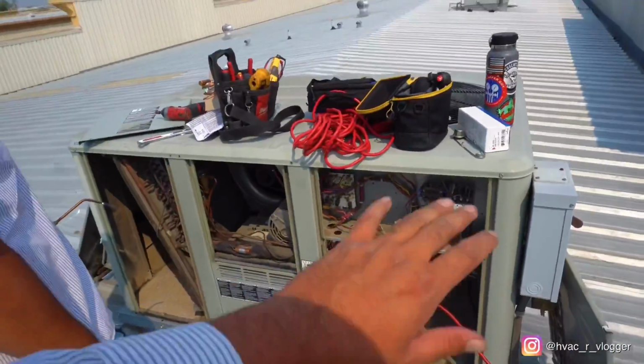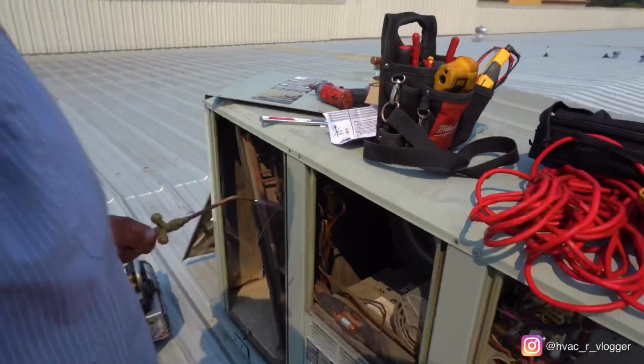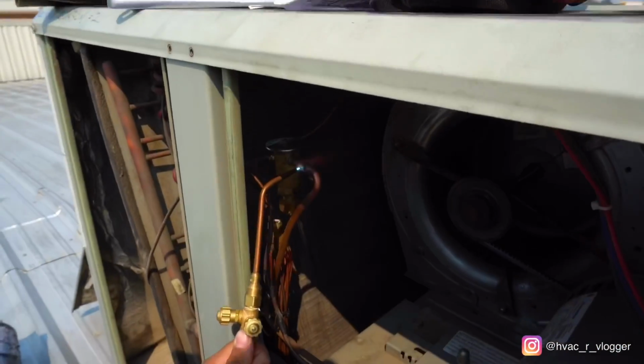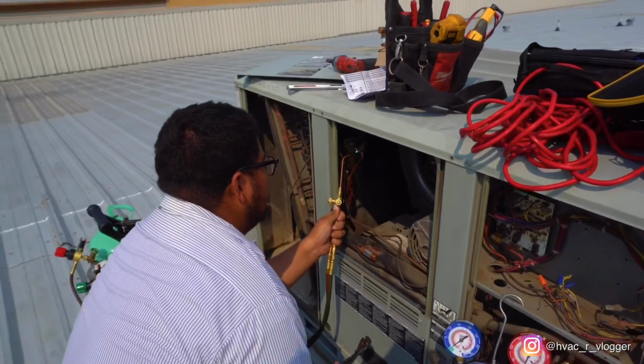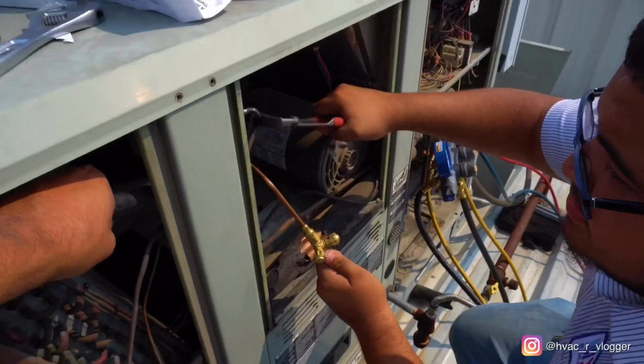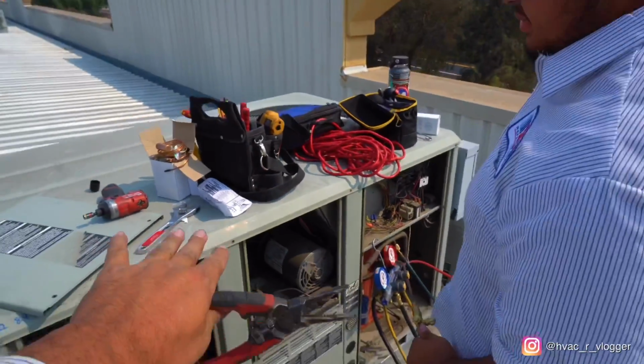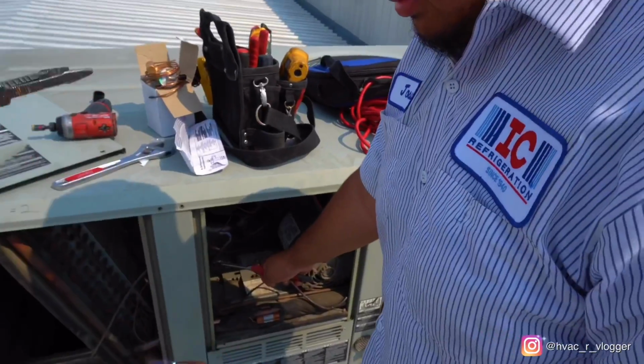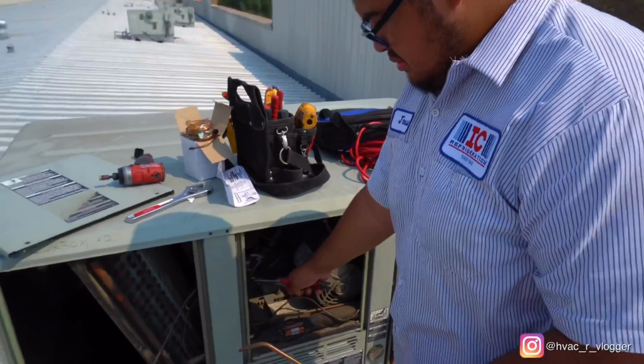And just a reminder, guys, it was completely flat on charge. So you're gonna go ahead and start. Yep. Yeah, go ahead and heat it up, and then pull it out. I'll tell you when to pull it out. There you go. Okay, so now, anytime you braze one, bro, hold it for like at least 5 seconds. Let it cool off. Because whenever they're hot, they'll go ahead and get stuck with each other.